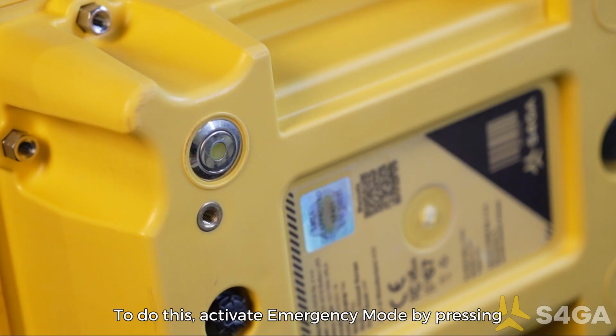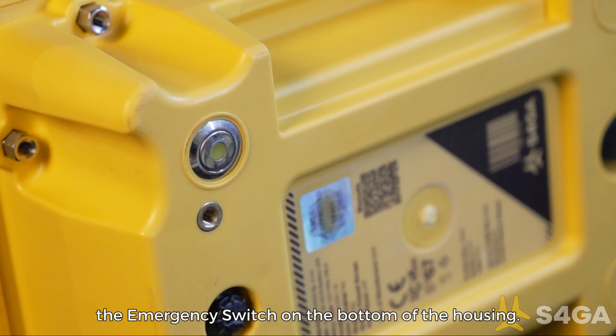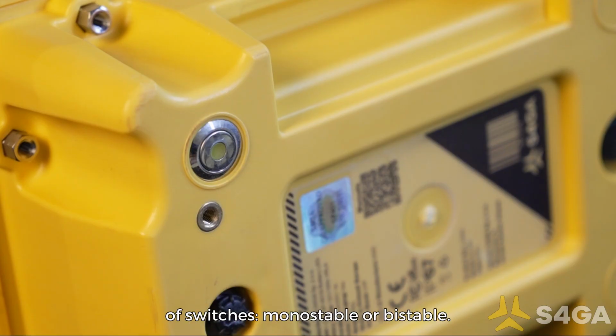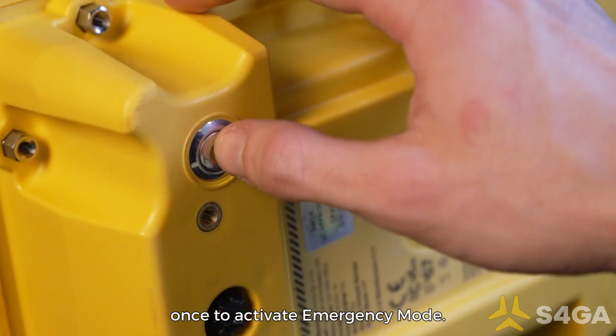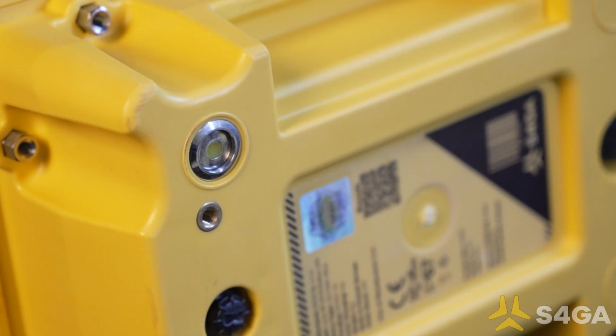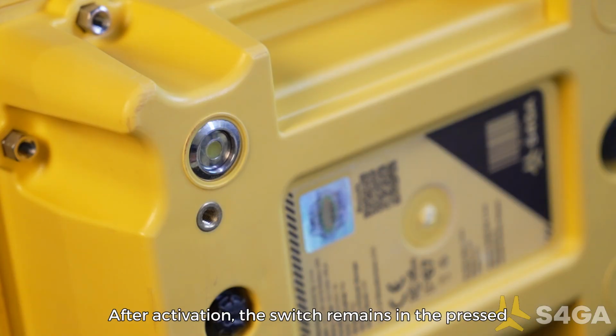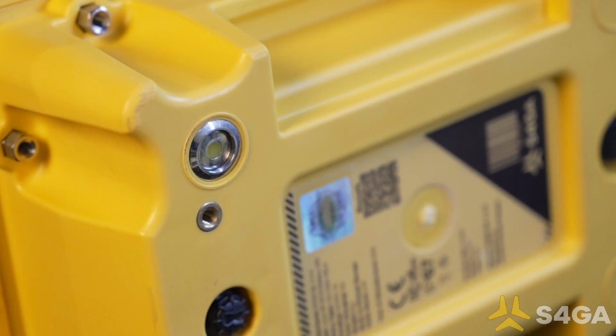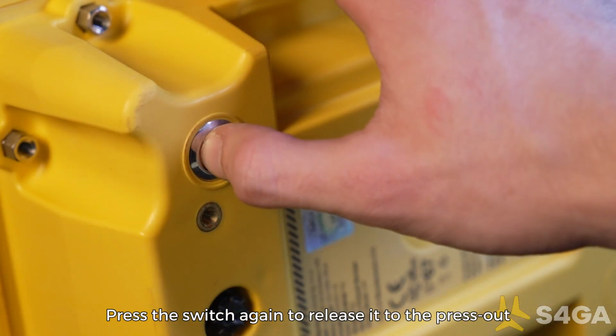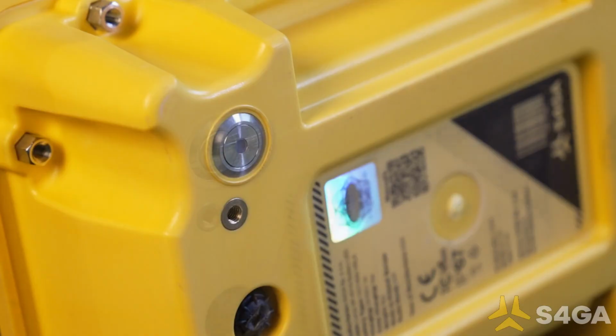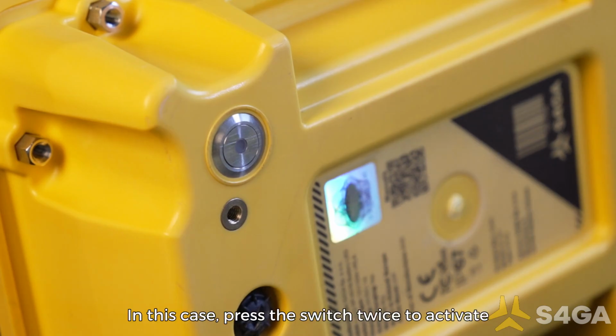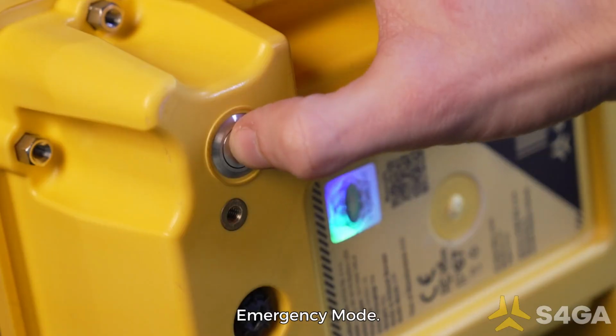To do this, activate emergency mode by pressing the emergency switch on the bottom of the housing. Your lamp may be equipped with two different types of switches, monostable or bistable. When using a bistable switch, press the switch once to activate emergency mode. After activation, the switch remains in the pressed position, which prevents deactivation. Press the switch again to release it to the press-out position and allow deactivation. When using a monostable emergency switch, the switch immediately returns to its original position after being pressed. In this case, press the switch twice to activate emergency mode.